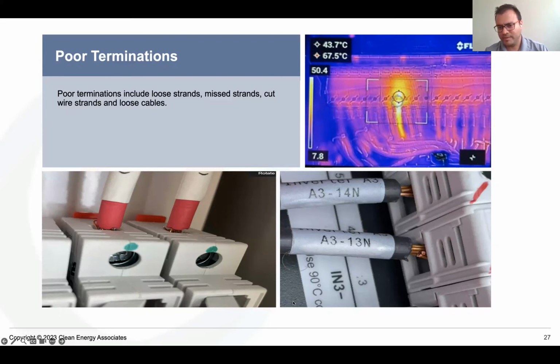On the right, the picture with the black cable that is labeled as A313N, you can see two cut strands on the cable. And these cables are not designed to be operated when they have damaged or cut strands. This increases the resistivity and this increases the heat signature. When we do the IR picture of these cables, you can see an example picture that we have that shows there is one cable that is heated compared to the rest of the cables, the one that is in yellow, that is shining.